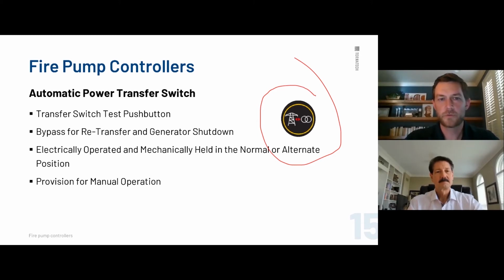The transfer switch needs to have a provision for manual operation, and it has an alarm for that. We need it to stay in the automatic mode. If it's been mechanically pushed over into the normal mode or the alternate mode and out of the automatic mode, that will send a signal. So that's just something that is required. With manual operation, if for some reason your automatic transfer switch is not working automatically, you can physically switch it over to the alternate position or switch it back over to the normal position. So it's just a bypass for that. But otherwise, it will be just left in the automatic position.